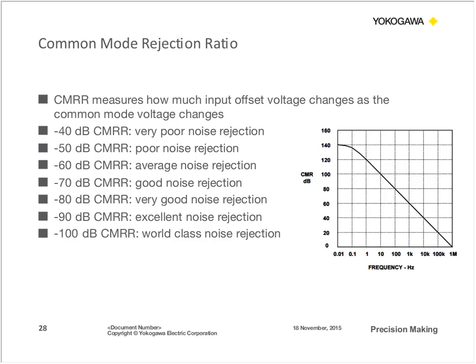Now, manufacturers typically represent the CMRR in decibels, and to really simplify how we can apply this, I've listed out here typical specs and how it affects your noise rejection and your ability to filter out that noise. So you can see at the very top, 40 dB common mode rejection ratio is very poor for rejecting noise. You're going to be measuring the signal with a lot of oscillating noise. And at the other end of the spectrum, if you have a 100 dB or greater CMRR specification, that's really world-class noise rejection that you're going to pay a lot of money for, for very high accuracy and sensitive measurements.